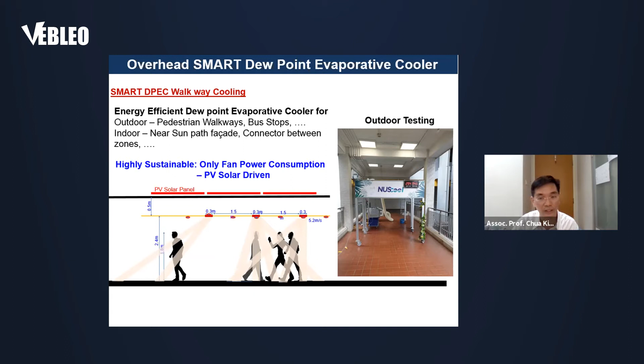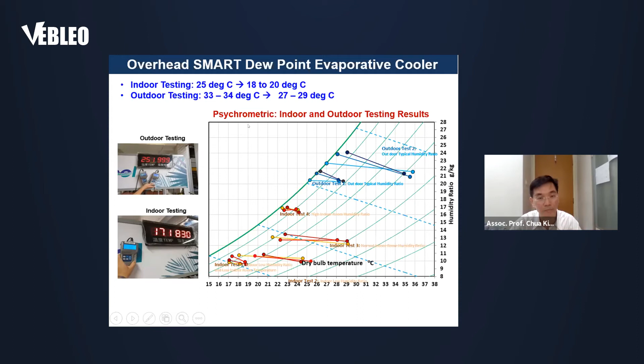We tested this outdoor without the membrane, just using the dew point cooler. We can bring down the air temperature by 5 to 6 degrees for outdoor cooling without the membrane. For indoor use, if the air is already fairly dry and cool, you can bring the temperature down even further, to 18 to 20 degrees, if you want much cooler air for part of your indoor environment.